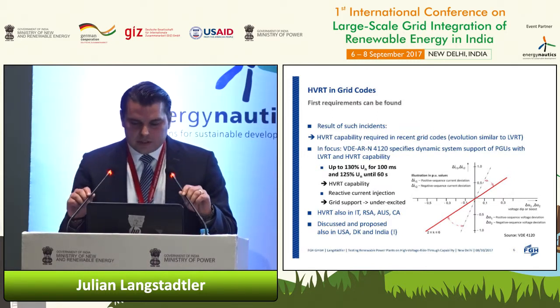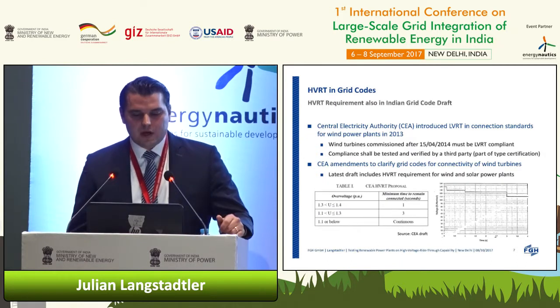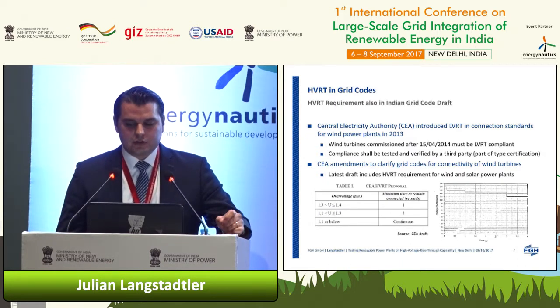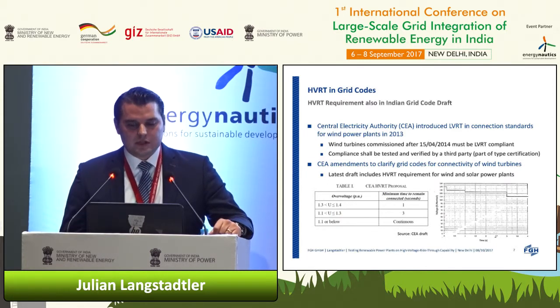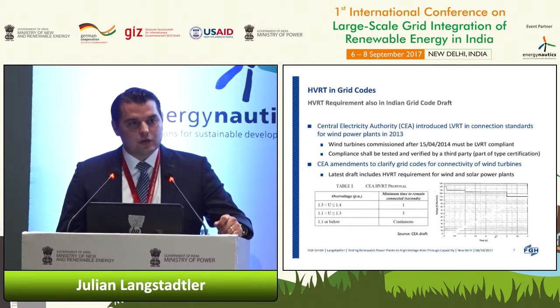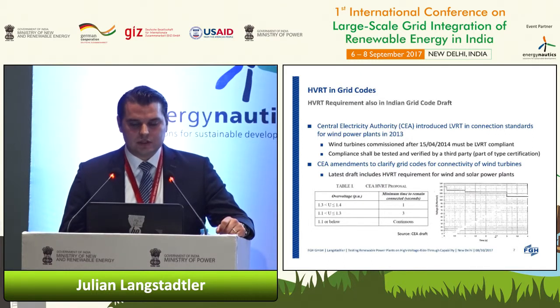So focusing on India again, so far the CEA introduced the LVRT requirement in the connection standards for wind power plants in 2013, and there is a fixed date, which is in 2014, after which commissioned wind turbines must be LVRT compliant. And this compliance shall be tested and verified by a third party and shall also be part of the type certification. However, in the recent amendment of the CEA grid code for connectivity of wind turbines, there was also an HVRT requirement introduced for wind and solar power plants, which was also mentioned today.